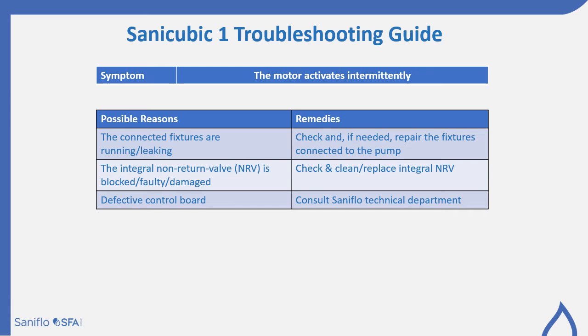The motor activates intermittently. It could be that the fixtures that are connected to the pump are running or leaking, therefore keeping the water level raised even though you may think you're not using any of the fixtures. So check and if needed, repair those fixtures connected to the pump.